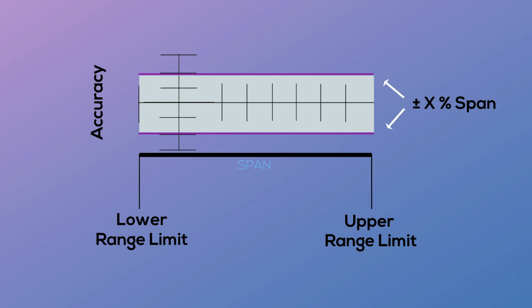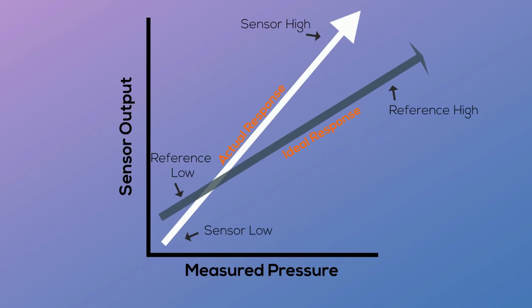acceptable limit. If no span adjust is available, verification of the full-scale reading is recorded, and pass-fail criteria determines whether the unit needs to be sent back for recalibration or is within the acceptable limits of the unit's span tolerance specifications. You have now completed a 2-point verification or calibration of a pressure transmitter. A multi-point run can also be performed by taking readings at incremental pressures and recording the equivalent output. A linear plot can then be drawn to determine the linearity of the device under test.